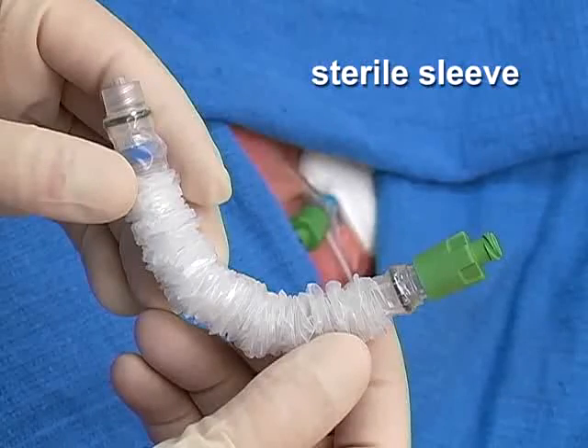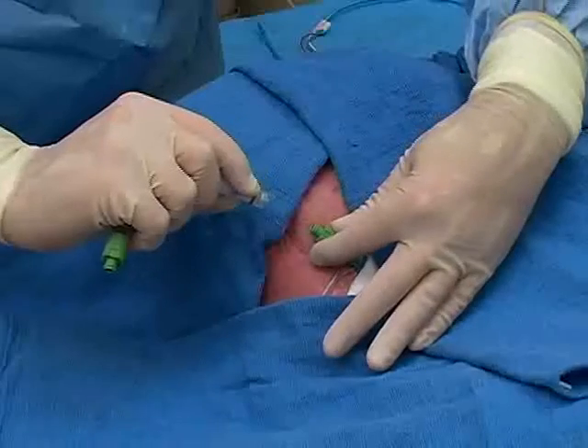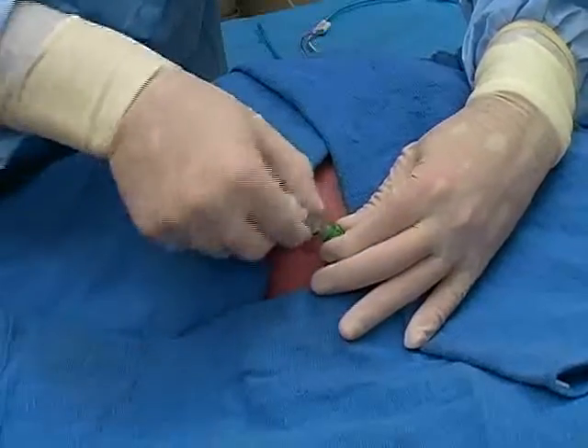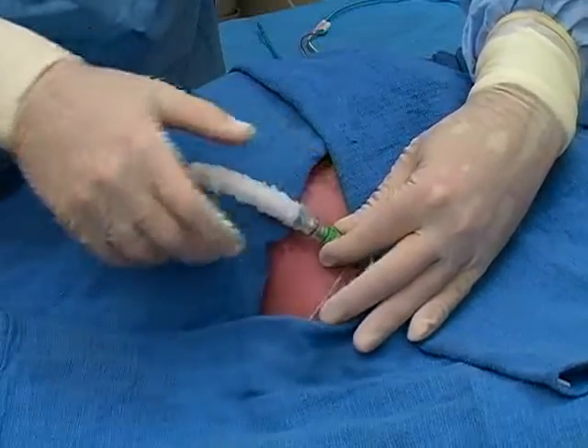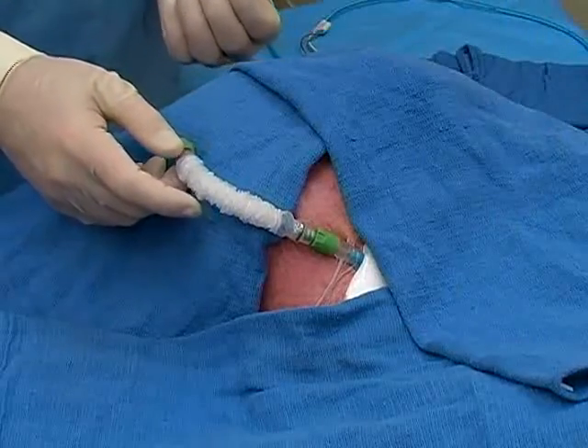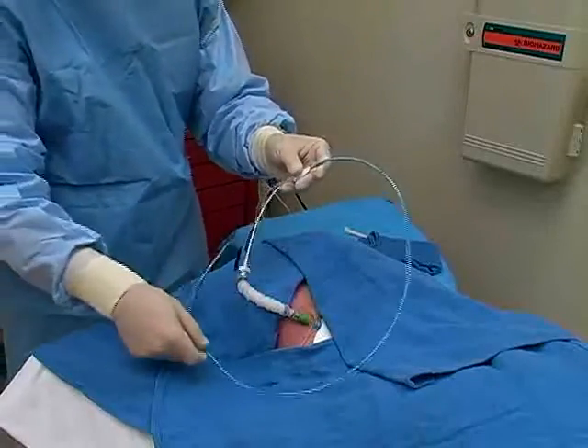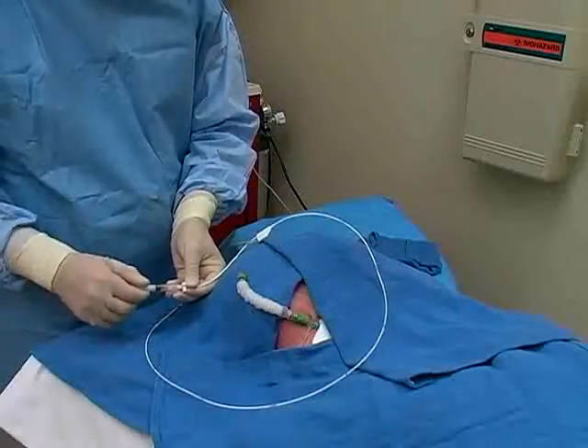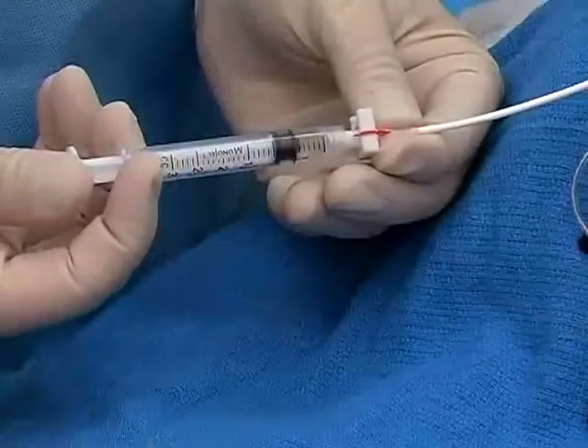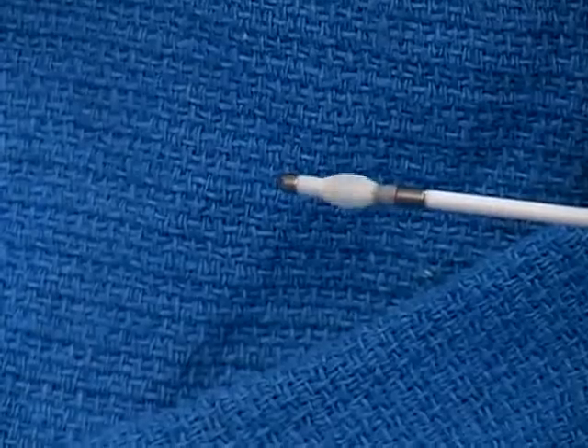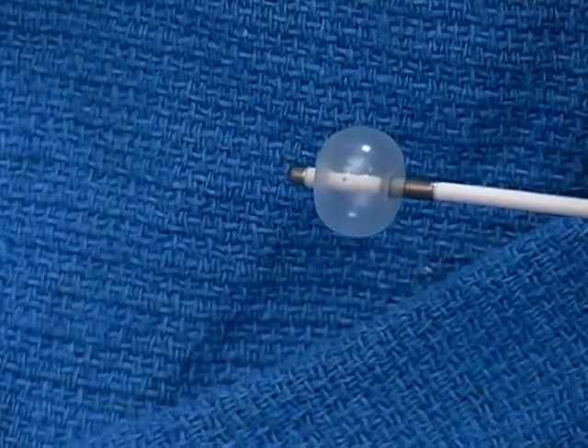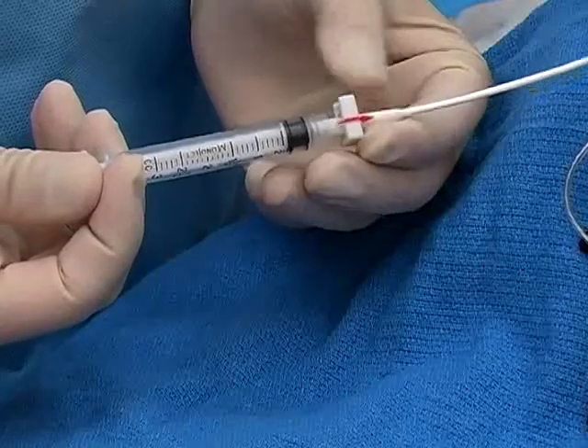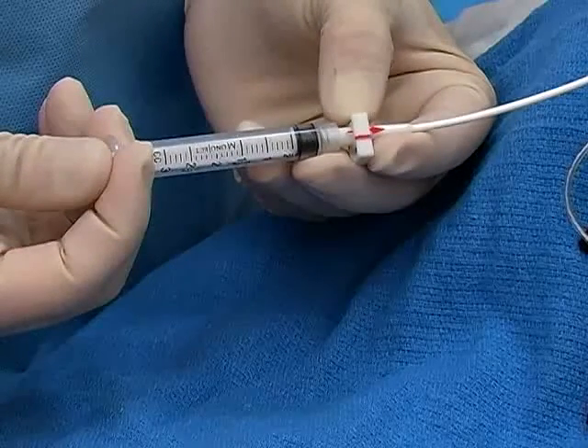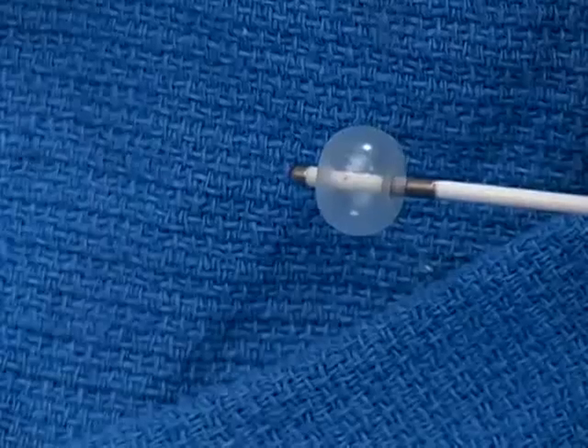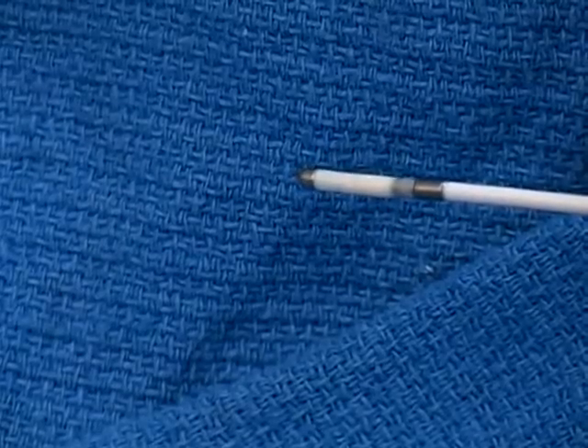Begin the procedure by attaching the sterile sleeve to the hub of the sheath introducer. Specific devices and connections will vary by manufacturer, so you should be familiar with the equipment available at your institution. Bring the pacing catheter to the sterile field. Test the balloon on the catheter by inflating it with the recommended amount of air, which is usually 1.3 to 1.5 milliliters. Note that the inflation port has a sliding gate valve that is used to keep the balloon inflated. Make sure that the balloon is fully deflated before proceeding.